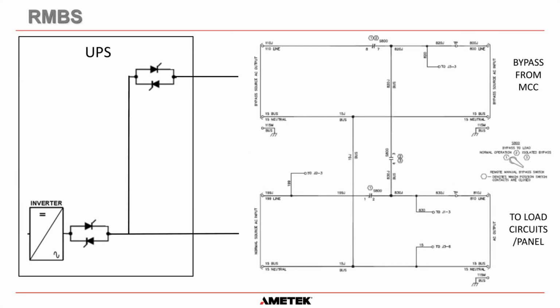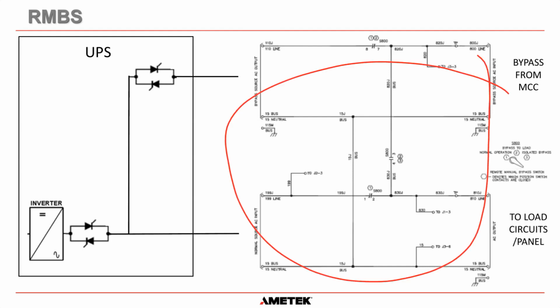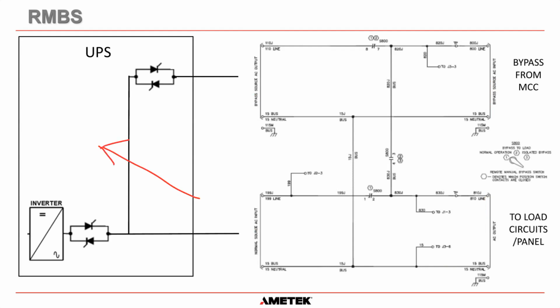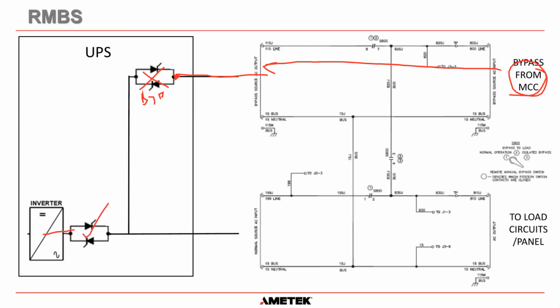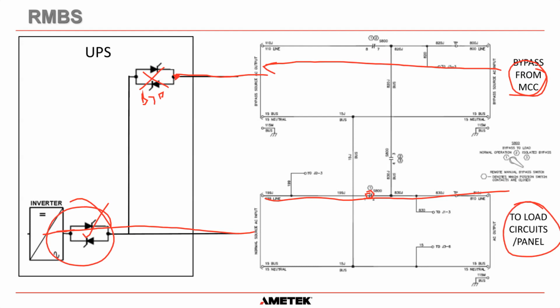And here's a simplified drawing of a remote manual bypass switch connected to a UPS. So remember, this section here is the RMBS, and this section here is the UPS. Okay, so you can see that first of all, our bypass comes from your MCC. It comes in and goes through the contact and comes here, goes into the bypass static switch. And remember, this is usually off, so it just stops there. Okay, and then the inverter is usually supplying power through the inverter static switch. Power will flow through here. You can see that this contact here is closed, so it will go through here and out to our load circuits. And you can see that this contact here is closed just now.